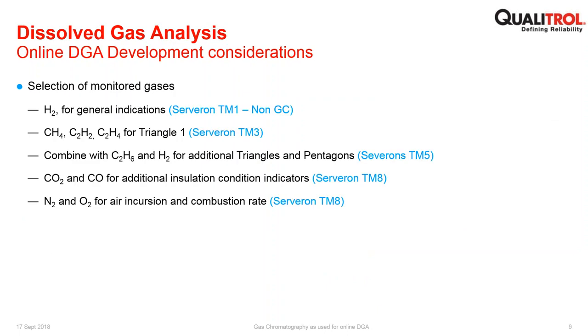From the point of view of the application of dissolved gas analysis, some of the things that need to be considered is how many gases you wish to measure. So we could consider that ideally you would measure all 9 gases, but there are cost implications to doing so. So there are different combinations of gas. For online dissolved gas analysis, some of the common applications are the measurement of just hydrogen as a general indicator of something happening or some fault developing in your transformer. It's considered to be an indicator gas or an alarm gas. If you see hydrogen being produced in appreciable amounts, you know that something is happening, and that can raise an alarm. Gas chromatography generally is not used for this simply because of the cost implications of using gas chromatography.